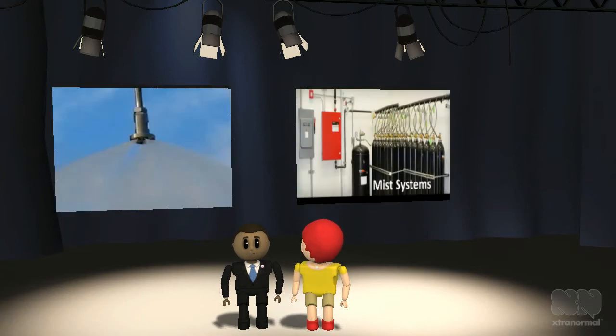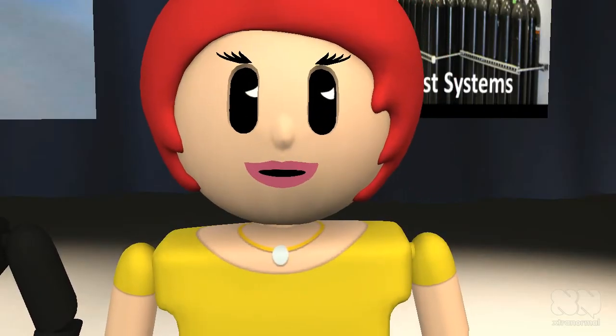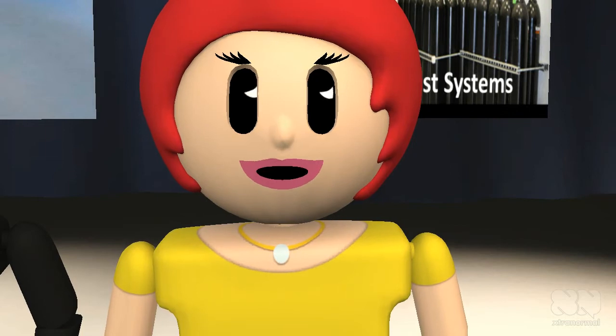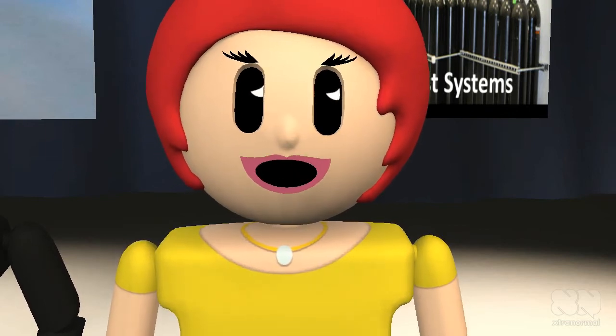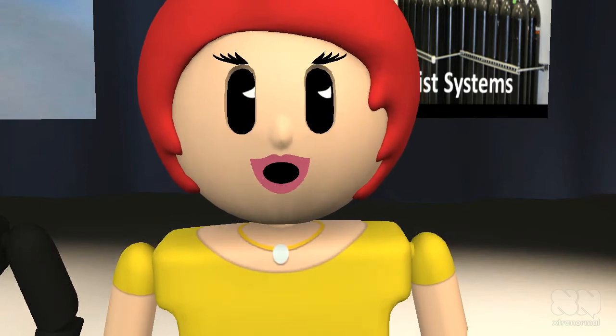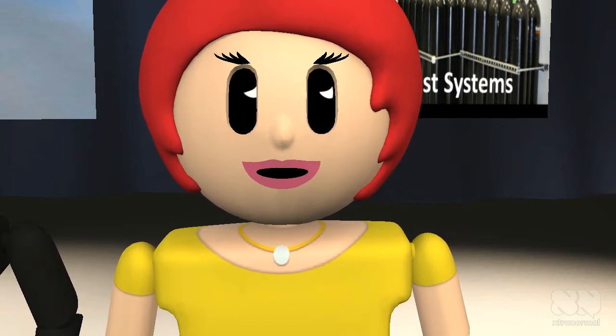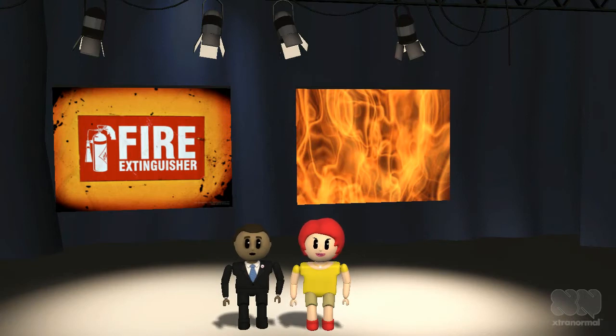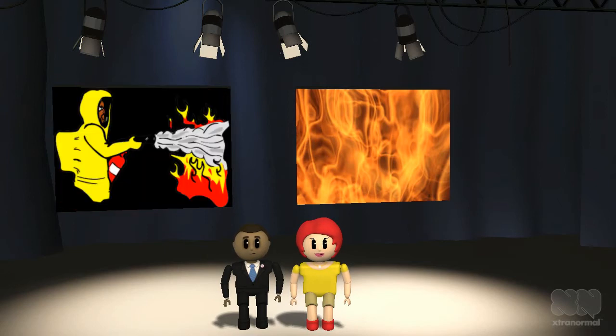We can also use a mist system. Mist systems were originally used for fires on ships. They allow a speedier initiation of the alarm and a quicker response to the fire than a sprinkler system. By using smaller volumes of water, mist systems reduce property damage. Another option is portable fire extinguishers. Portable fire extinguishers are used to extinguish fires at an early stage. These extinguishers are movable and do not require access to plumbing lines. They are rated for the class of fire they are designed to fight. The number of portable fire extinguishers required and their locations depend on the hazard classification of the occupancy. They must be located in an accessible place along the means of egress.